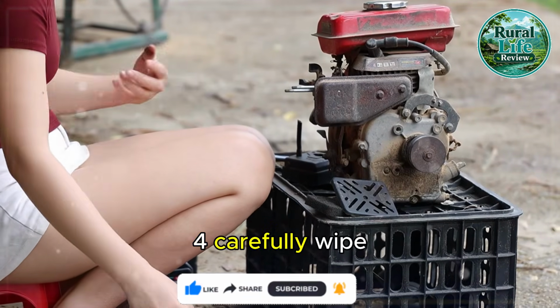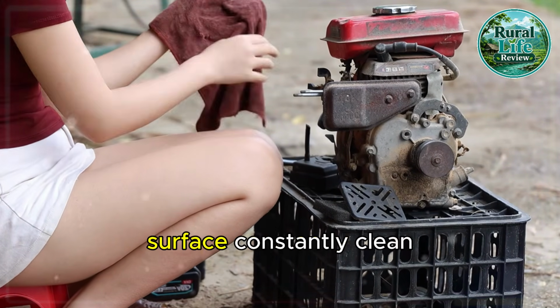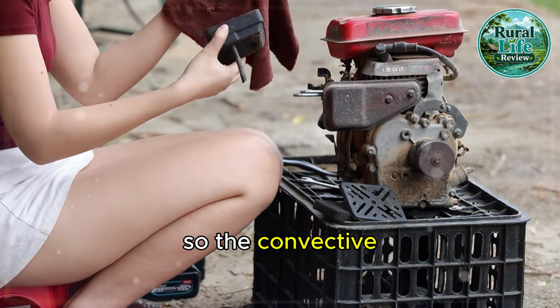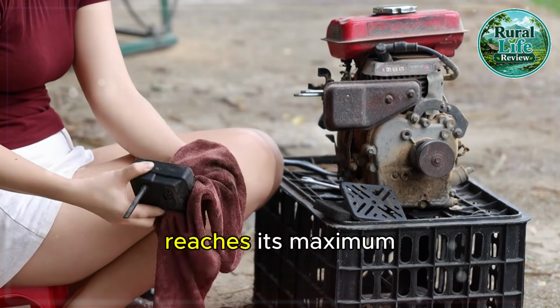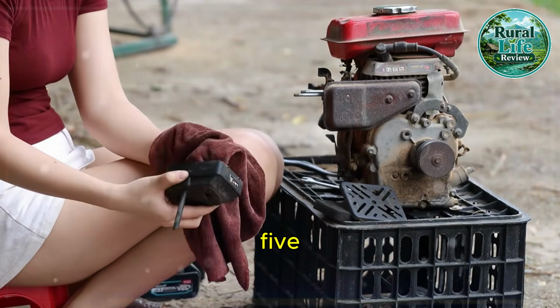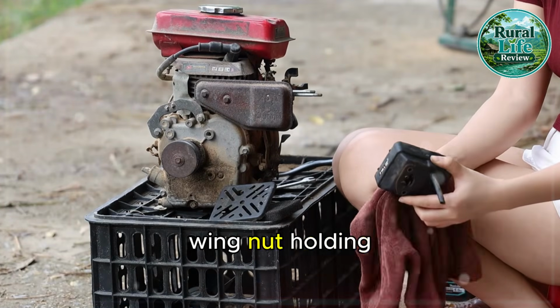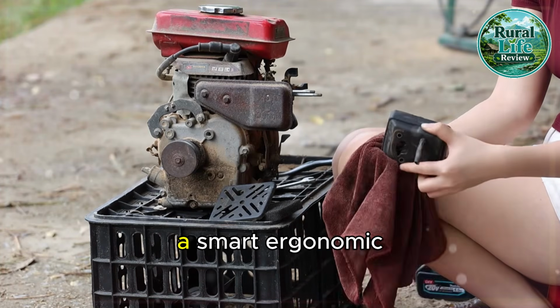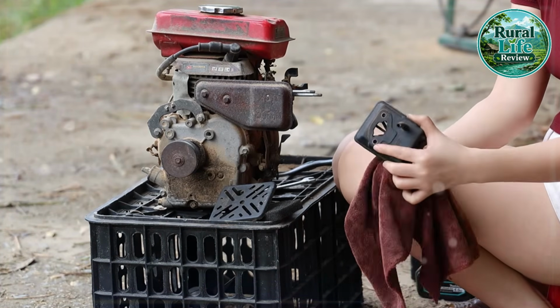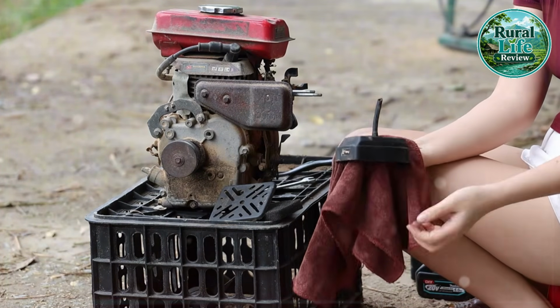mechanical vibration. 4. Carefully wipe the outer cooling fins, keeping the alloy surface constantly clean so the convective heat transfer coefficient reaches its maximum. 5. Hand tighten the wing nut holding the air filter cover. A smart ergonomic design for quick maintenance out in the field.